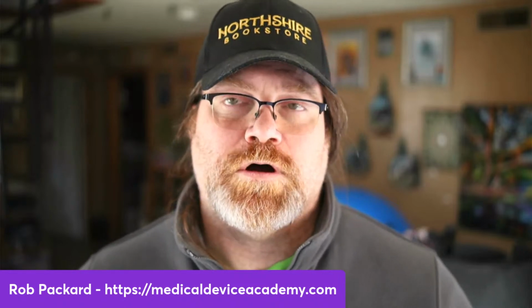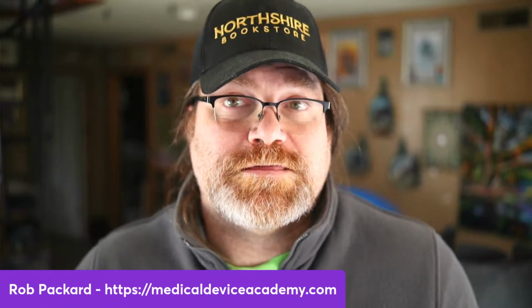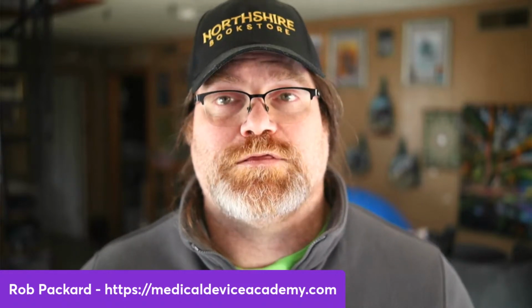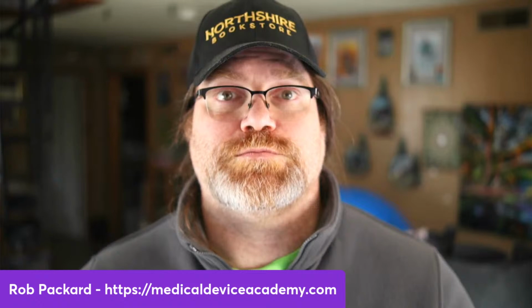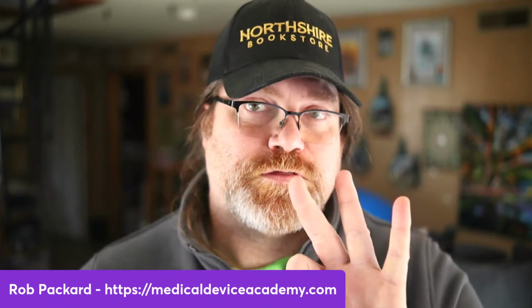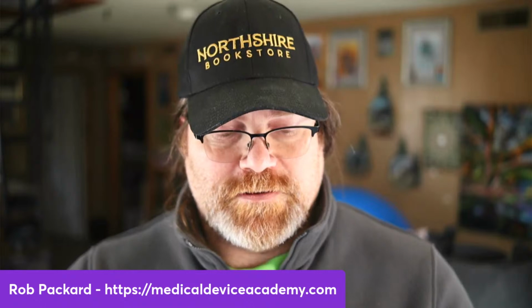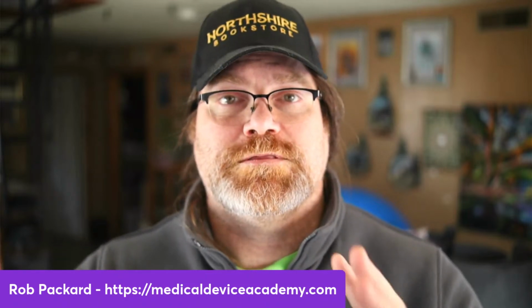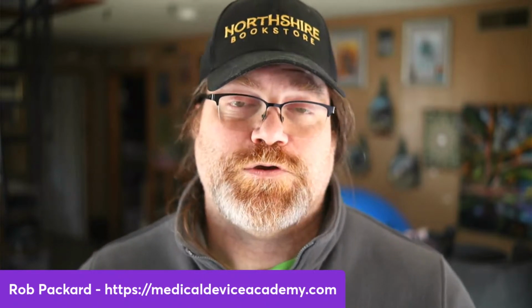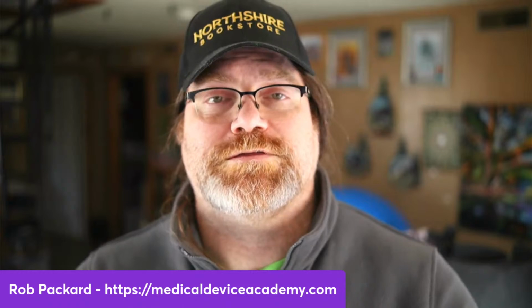They don't take that long. It's hours of work, not days of work. But what causes time is we're waiting for the client to give us a device description, give us a user manual, give us a test protocol. So those are the three things you put in there: device description, user manual, testing protocol. And that's what you need for each of your questions in a pre-sub.